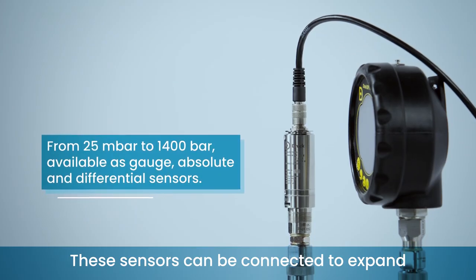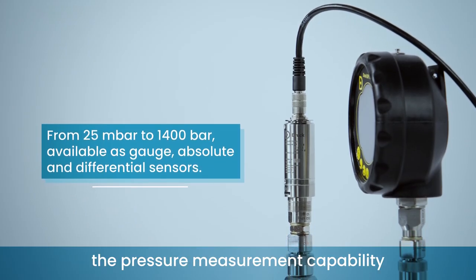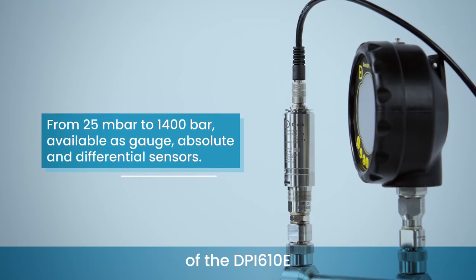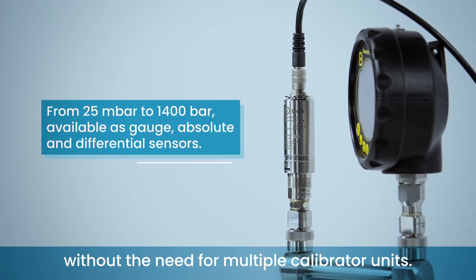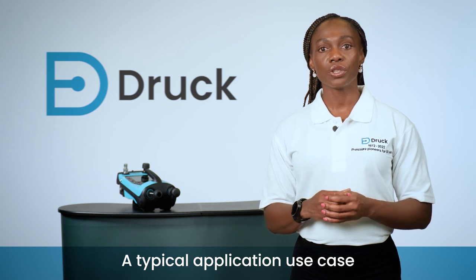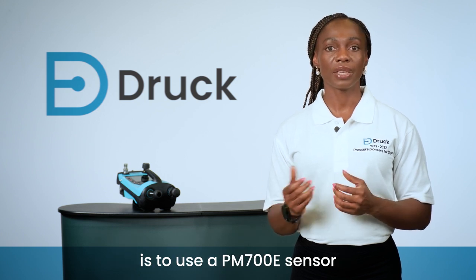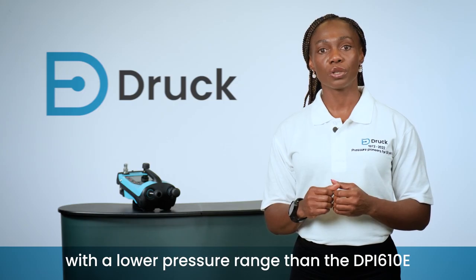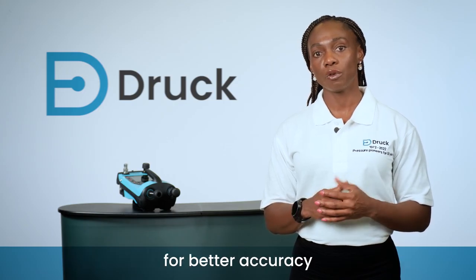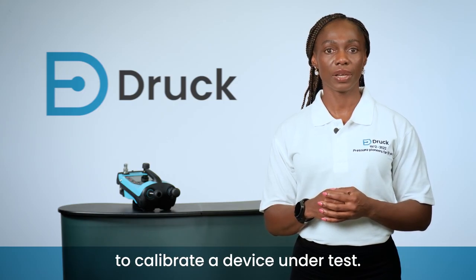These sensors can be connected to expand the pressure measurement capability of the DPI610E without the need for multiple calibrator units. A typical application use case is to use a PM700E sensor with a lower pressure range than the DPI610E for better accuracy to calibrate a device under test.